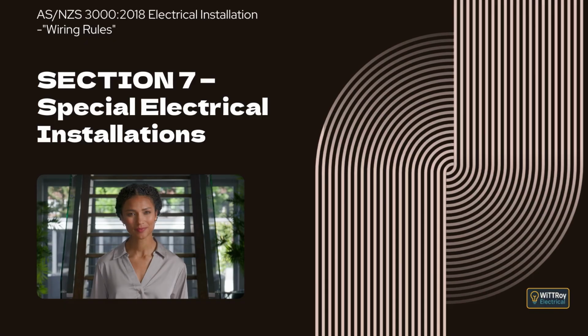This clause explains that air handling systems used to control fire and smoke movement are safety services and must therefore meet the requirements that ensure reliable operation during emergencies. Clause 7.2.7.2 Wiring systems for air handling systems. This clause introduces the wiring requirements for air handling systems used for fire and smoke control.